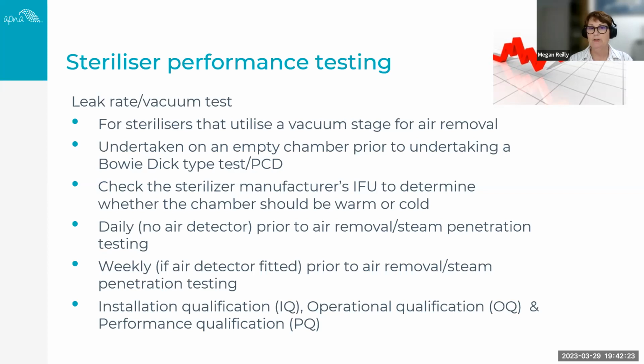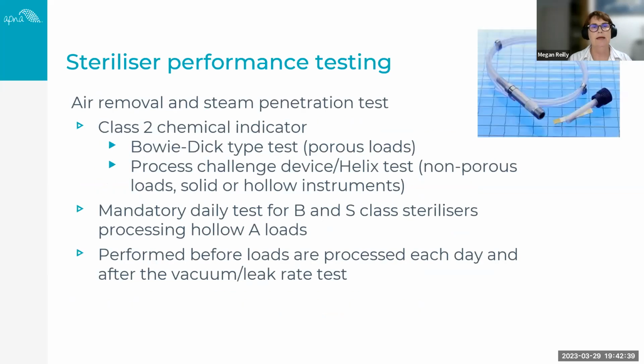Also, how frequently you need to do that will depend on whether you have an air detector in your steam sterilizer or not. And also, this test is always carried out at installation, operational qualification and performance qualification by your service provider. The air removal or the steam penetration test, which is our class 2 chemical indicator, is often referred to as a Bowie-Dick or a process challenge device or helix test.